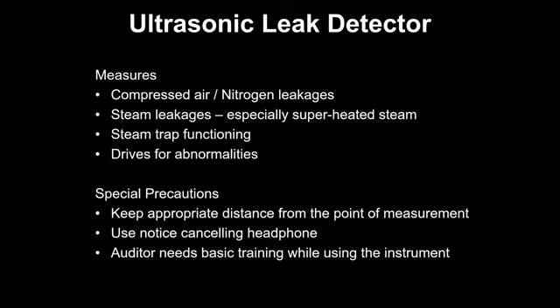But this coupled with thermography can tell you the trap health. So we normally do this trap testing with ultrasonic plus thermography to get correct values. It will also give abnormalities of the drives, because if there is some misalignment or any issues, the sound will be of different types. There are specialized gadgets made only to do this test also, but our normal ultrasonic detector also can do the functioning. May not be as accurate, but it can be sufficient for us.